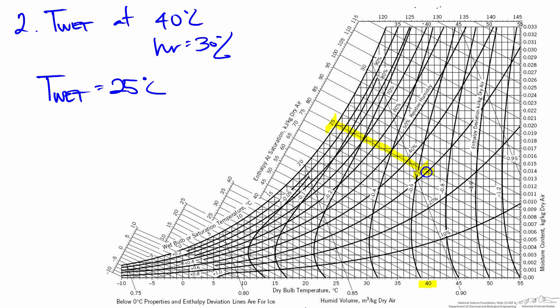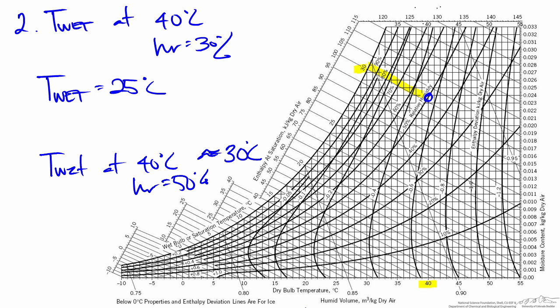So here the wet bulb temperature is about 25 degrees, which is substantially lower than 40 degrees due to the relatively low moisture content at 30% relative humidity. To illustrate how this changes as a function of moisture content, let's look at the example where we are at 40 degrees and 50% relative humidity. Moving along a different line of constant wet bulb temperature diagonally up and left to the saturation curve, we can see that the wet bulb temperature is something greater than 30 degrees — between 30 and 31. As we would expect, increasing the relative humidity increases the wet bulb temperature, and as we approach 100% relative humidity the wet bulb temperature would approach the dry bulb temperature of 40 degrees.